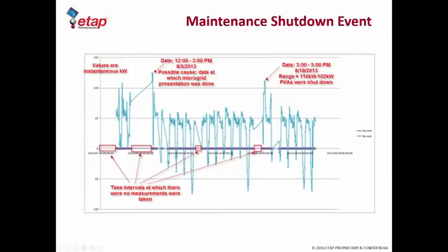at this particular date on August 19th, we were somewhere in the range of 102 to 110 kilowatts. Everything was fine. We were generating power, and we had an outage on the inverter. So as soon as we had an outage, we hit the maximum demand for that month, and obviously we were billed the maximum demand charge for that month. But you can see overall for the month we were doing very well till that outage event happened.